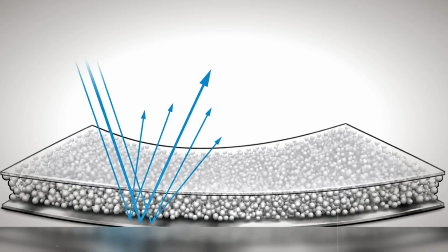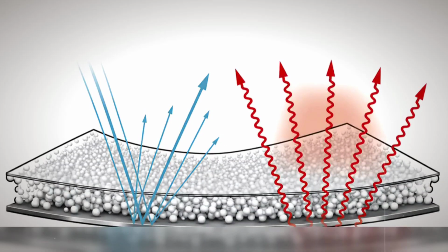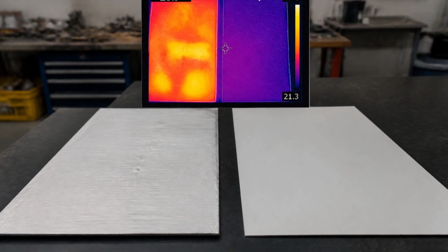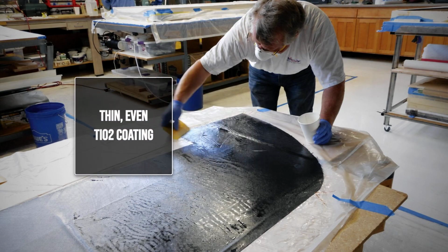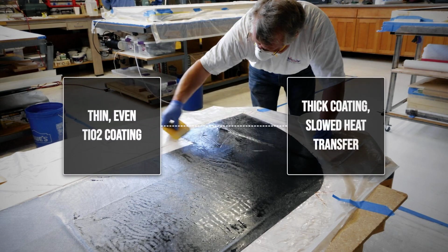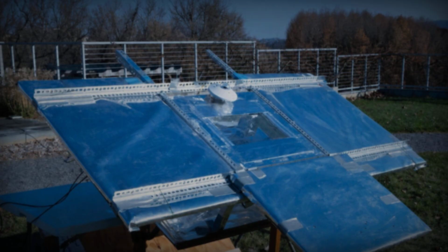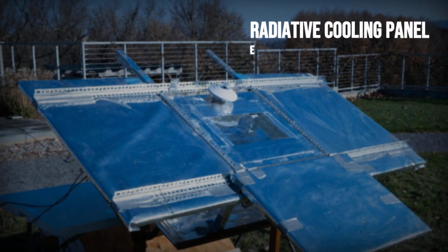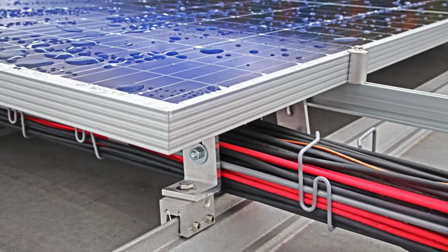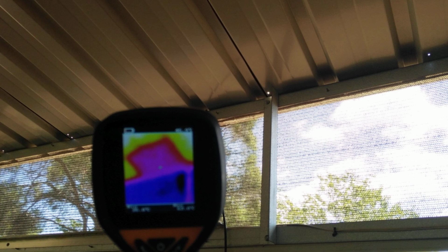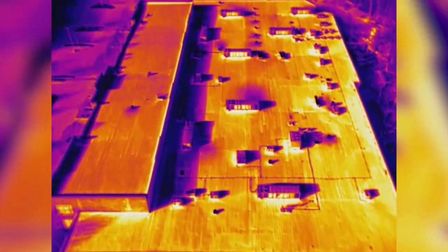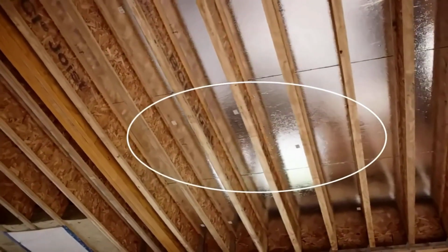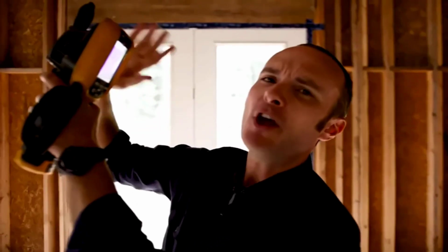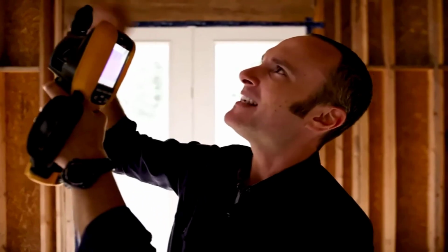The coating should be applied in several thin, even layers, rather than one heavy layer. Uneven paint can create areas with different thermal behavior, while excessively thick coatings may slow heat transfer between the metal and the surface. Once the emitter is prepared, it needs to be isolated from unwanted heat. Placing the aluminum directly against a hot roof would allow heat from the roof to flow into the panel. The panel might still radiate upward, but much of its cooling capacity would be spent removing heat from the roofing material instead of cooling the intended water or air loop.